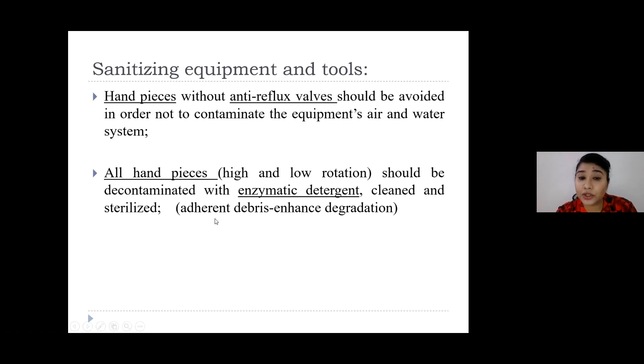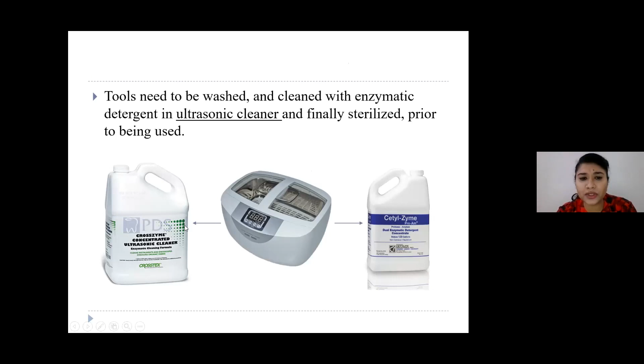See, we use ultrasonic cleaners. We get the enzymatic detergent with that. It is manufacturer designed. And this enzymatic detergent helps the adherent debris to be removed by enhancing their degradation. And the other instruments which we use have to be religiously washed and cleaned by using the enzymatic detergent in this ultrasonic cleaner. These are the two brands which are readily available.